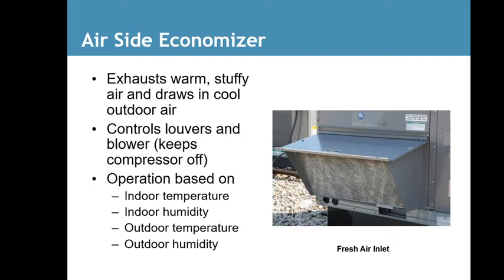Air side economizers. In a nutshell, what an economizer does, and to make it easier for you to understand, think of a bank building, let's say 2 stories, in a place where it's 50 or 60 degrees in the winter, somewhere like Florida or somewhere a little farther north. There's really no need for heat. When you're working in that office building, with a whole bunch of cubicles, and there's a person, a computer, lights overhead, it gets warm in there. So even though it's 60 or 50 or maybe even 40 degrees outside, inside that office will get very stuffy.